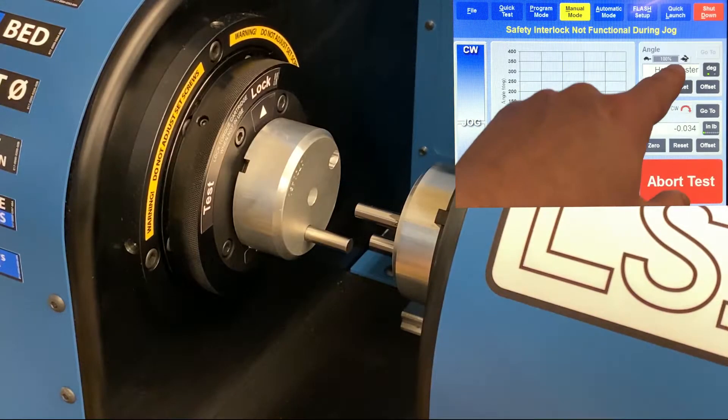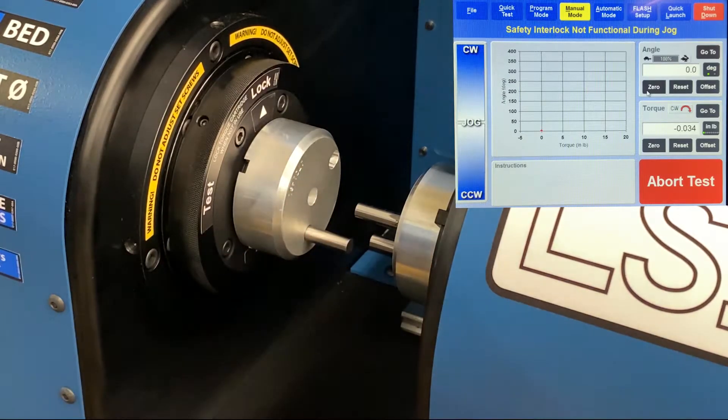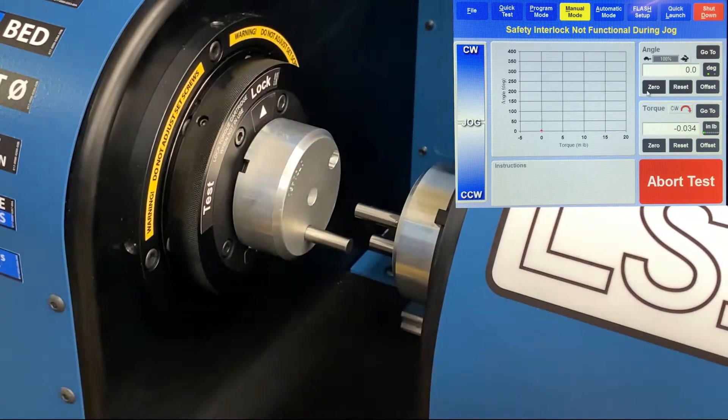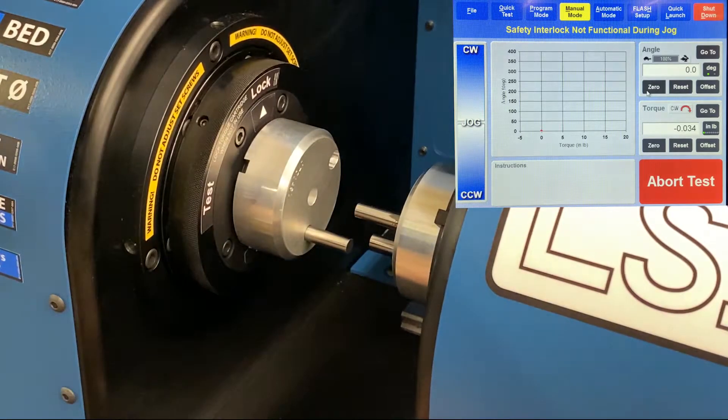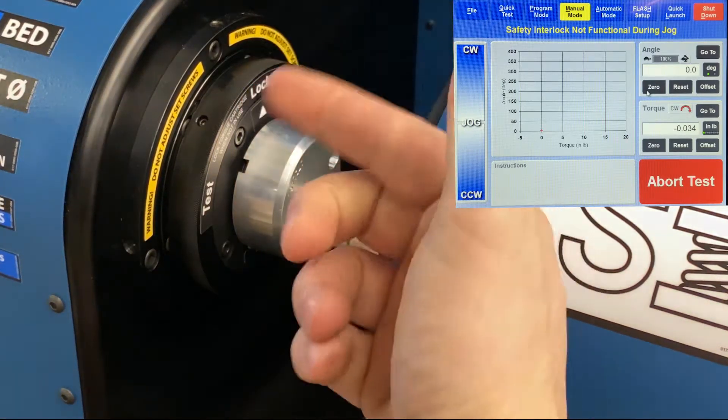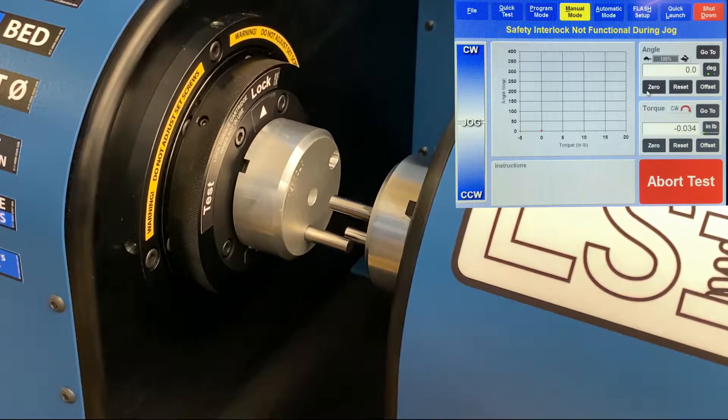Okay, so we're going to home the tester so that it has an angle to start from while we try to line up these custom tooling plates. I'm going to bring it close together, and I can tell that I got to move counterclockwise, so I'm going to do that manually.